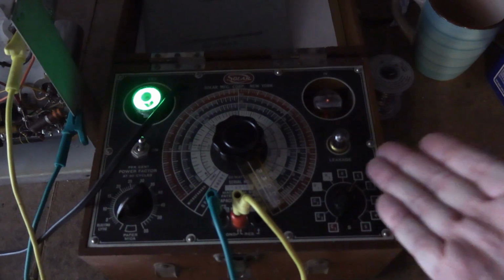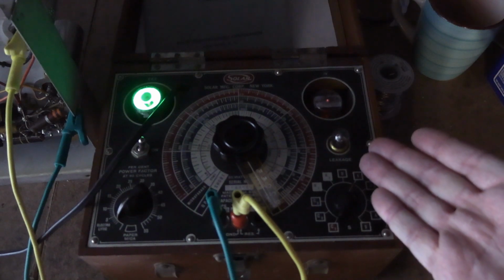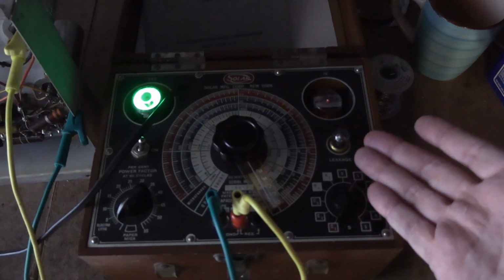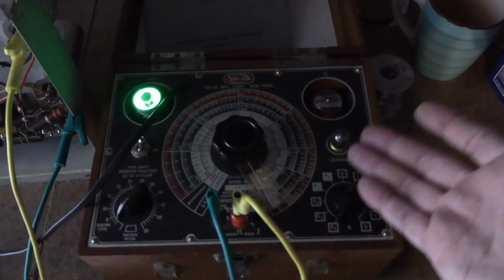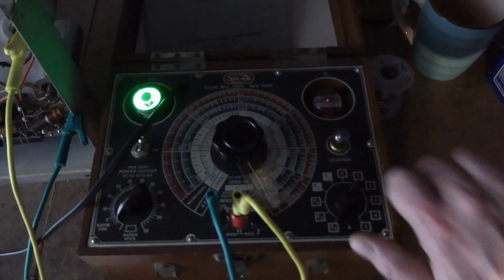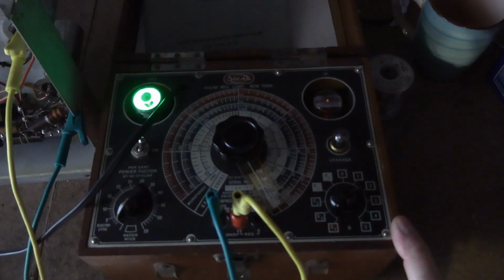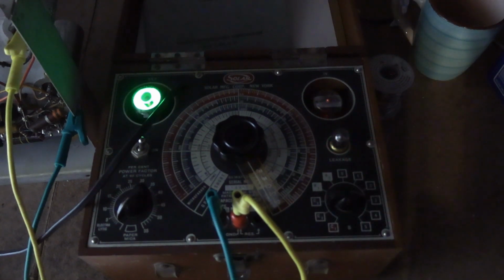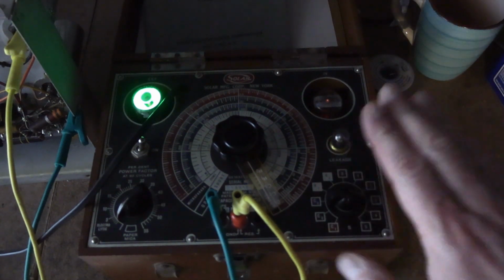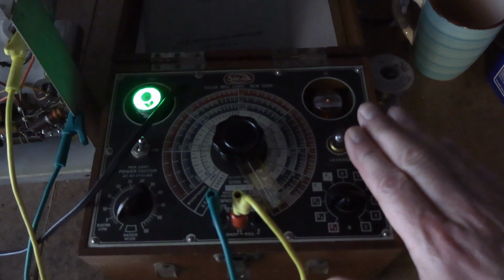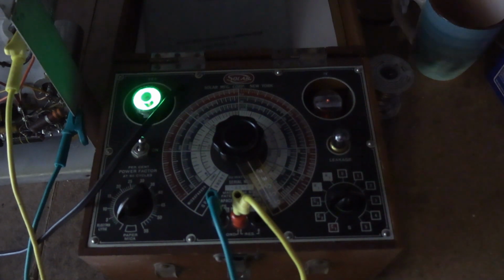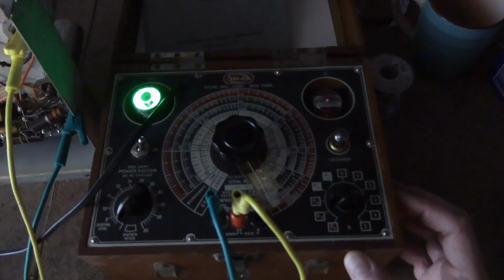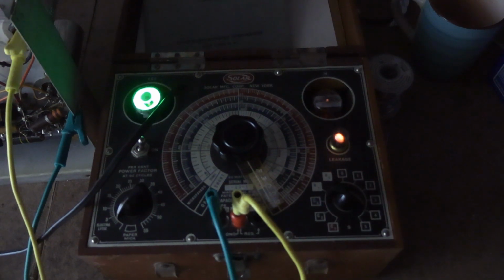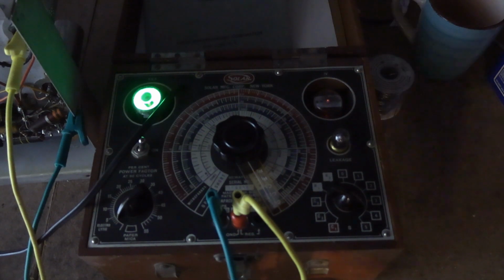So at 100 volts, we have no leakage. If there was a tiny amount, this might flash once every 10 or 15 seconds. We've got no flashing. Let's go 200 — excellent. 300 — lit up, no problem, that was charging up to the higher voltage level, and it's staying off. 400 — now it's struggling a little bit, but it did go out.